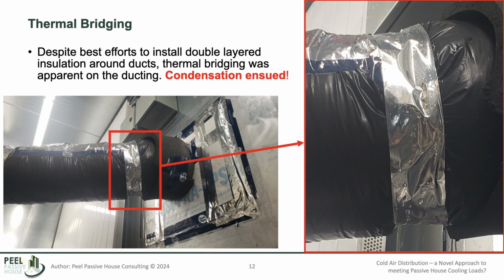Another issue was thermal bridging. I had this nice metal duct, double insulated with fiberglass duct insulation, vapor sealed and taped, but I still got condensation. Obviously there was a weakness in that insulation somehow—you do your best, but there's a lot going on in the lab, and you get condensation.